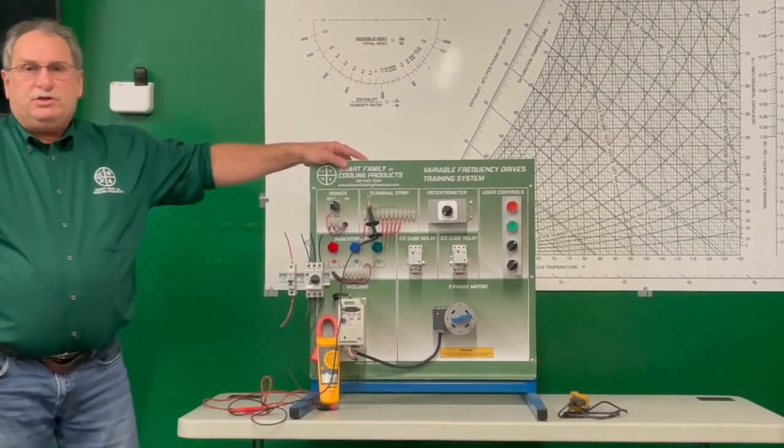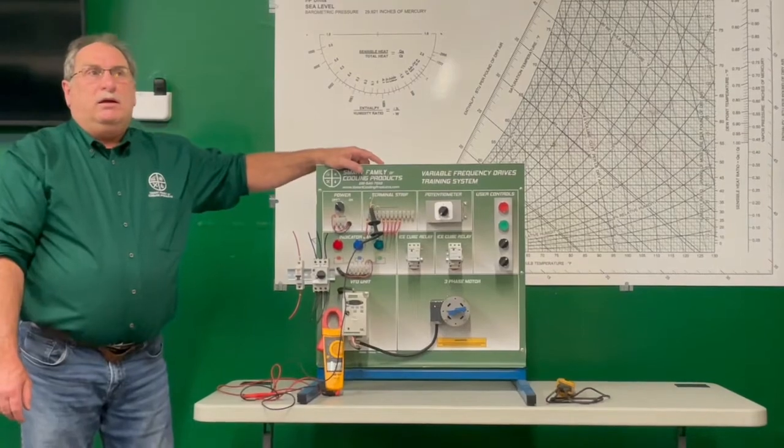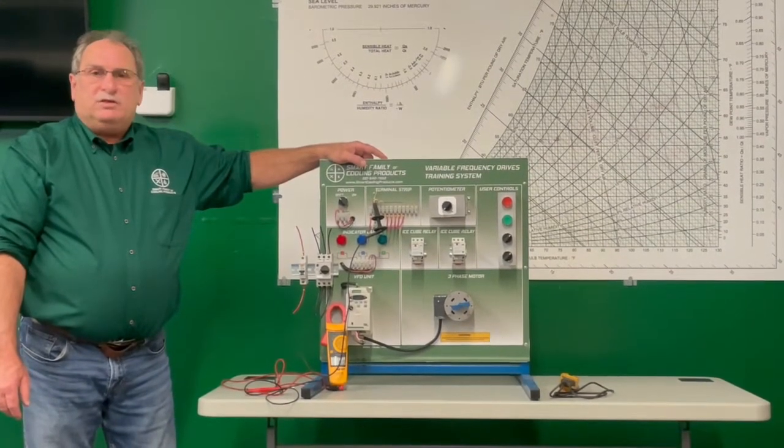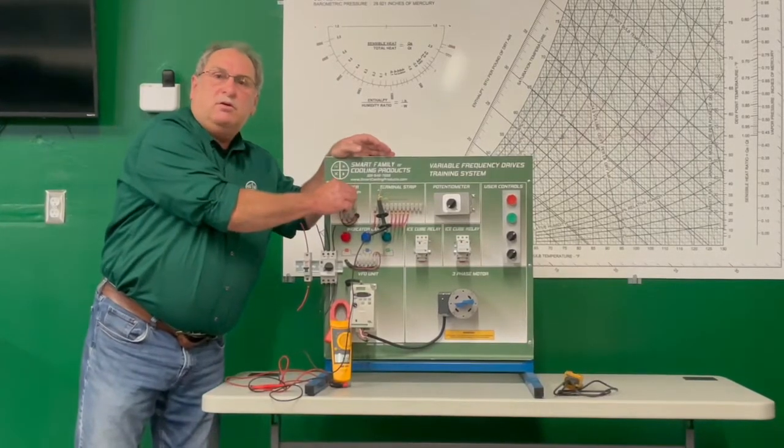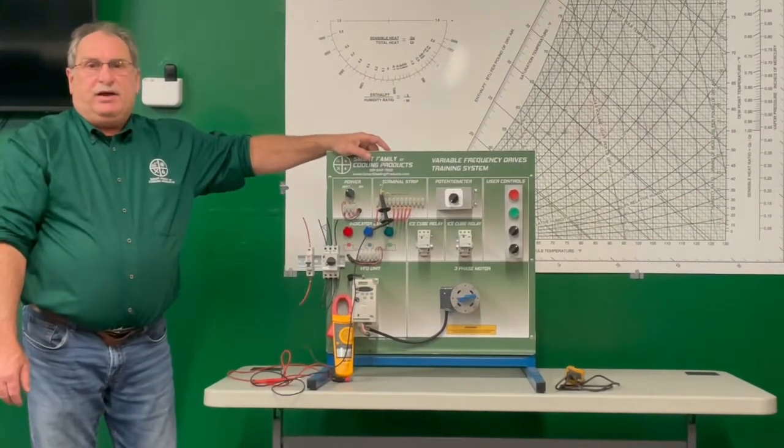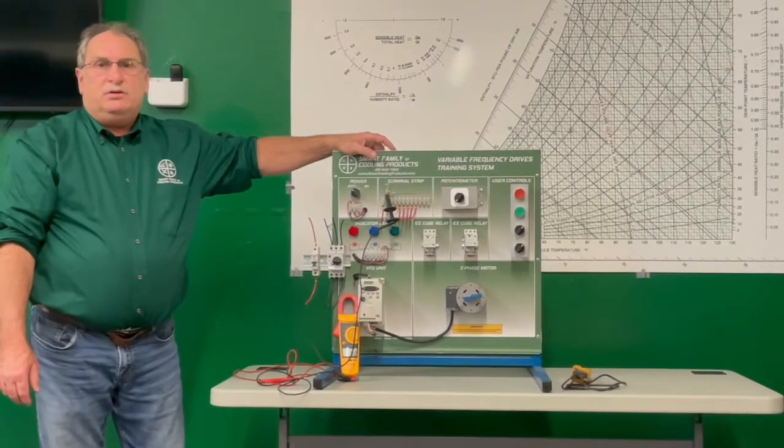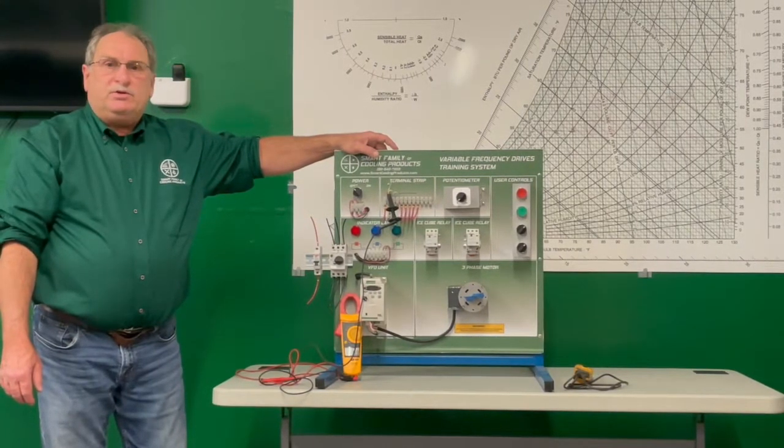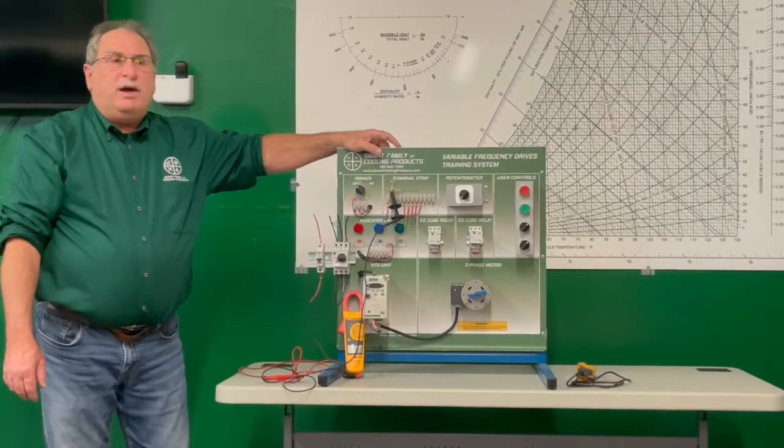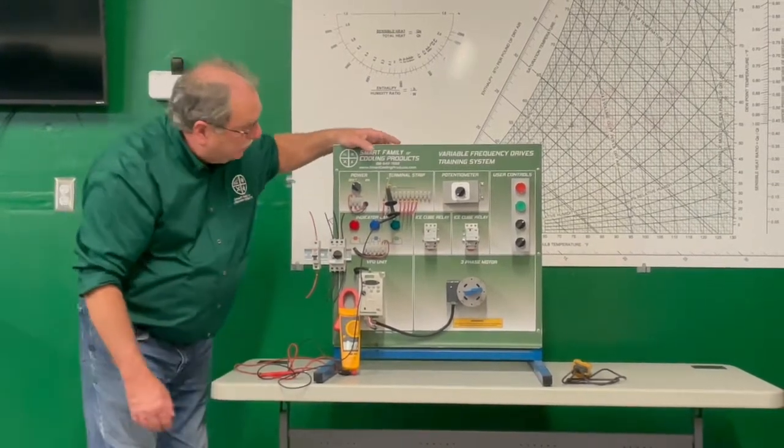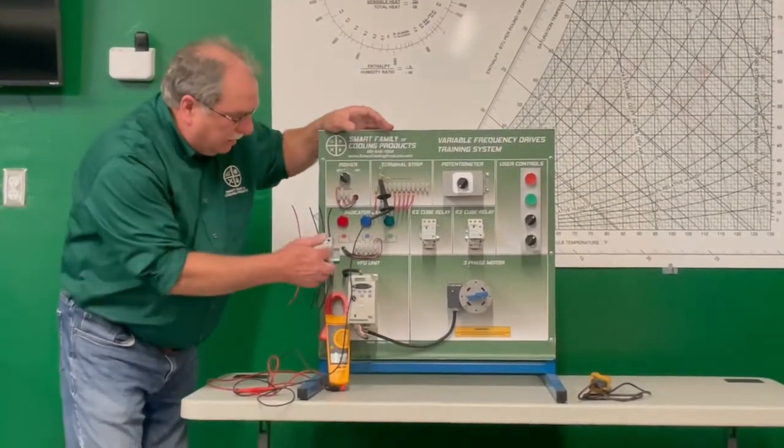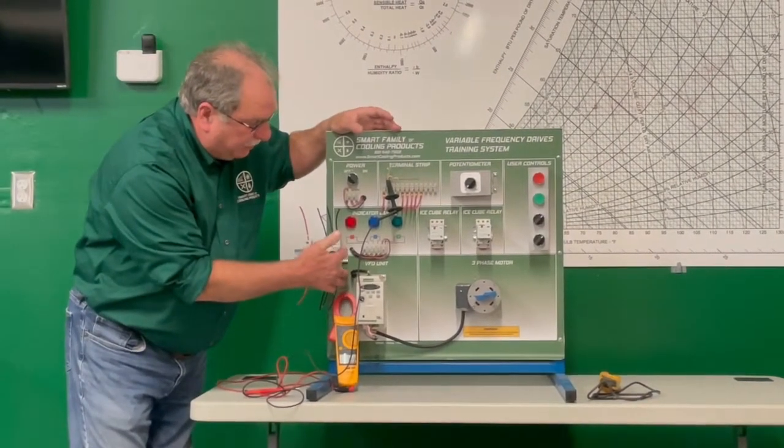Likely it's a switch or, for example, a flow switch or a selector switch or something like that. That might be a safety device like a motor protection module. That might be a high pressure switch or a low pressure switch. That might even be an auxiliary contact. I don't see one here, but sometimes on the side of the breakers we have an auxiliary contact.